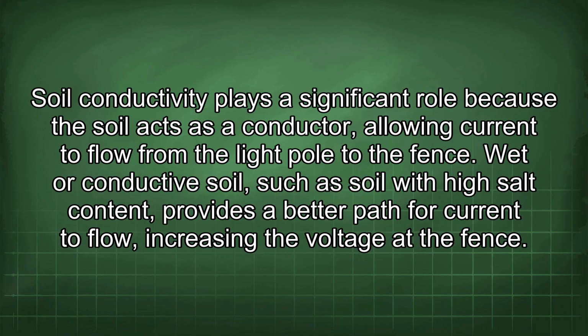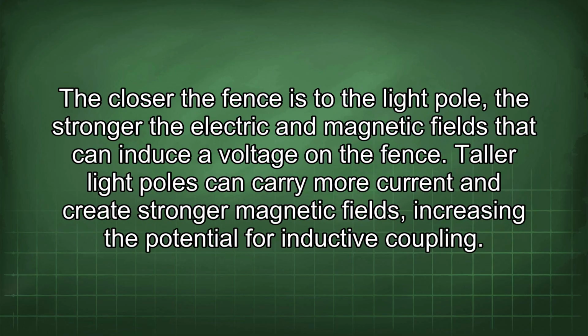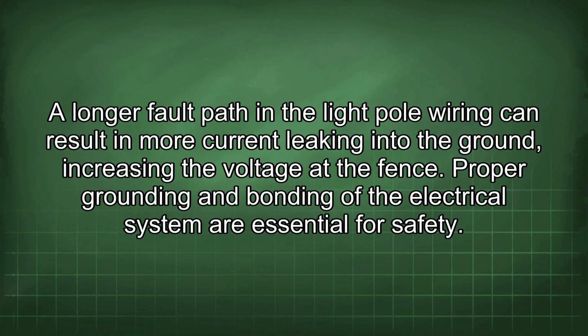Soil conductivity plays a significant role because the soil acts as a conductor, allowing current to flow from the light pole to the fence. Wet or conductive soil, such as soil with high salt content, provides a better path for current to flow, increasing the voltage at the fence. The closer the fence is to the light pole, the stronger the electric and magnetic fields that can induce a voltage on the fence. Taller light poles can carry more current and create stronger magnetic fields, increasing the potential for inductive coupling. A longer fault path in the light pole wiring can result in more current leaking into the ground, increasing the voltage at the fence.